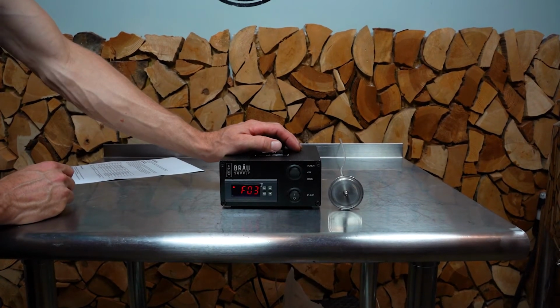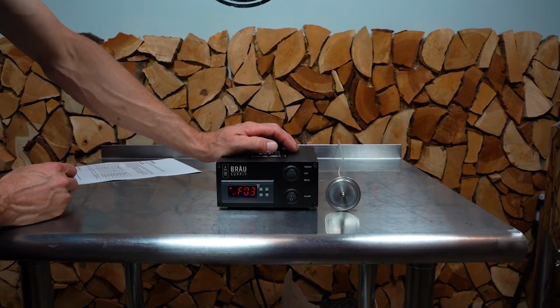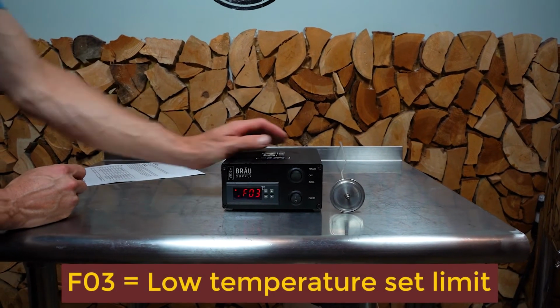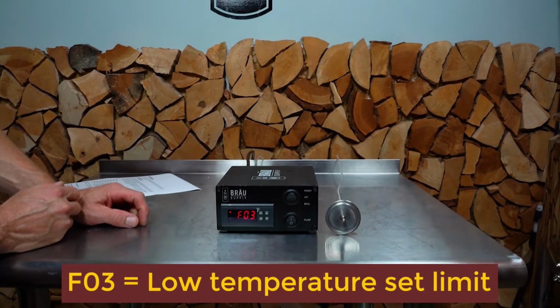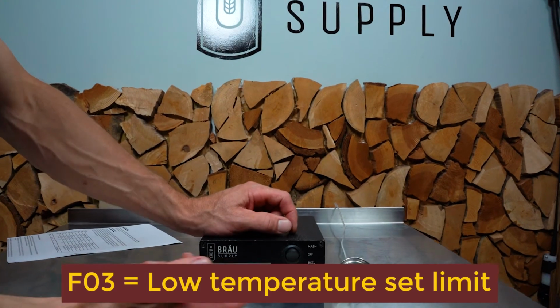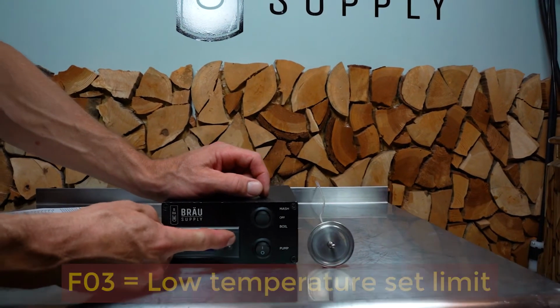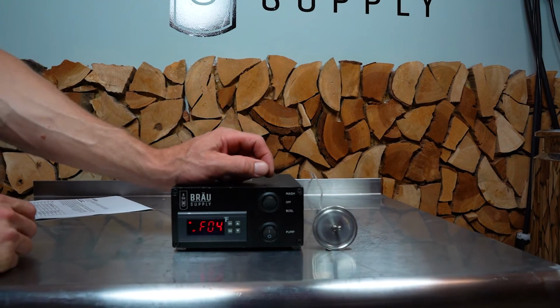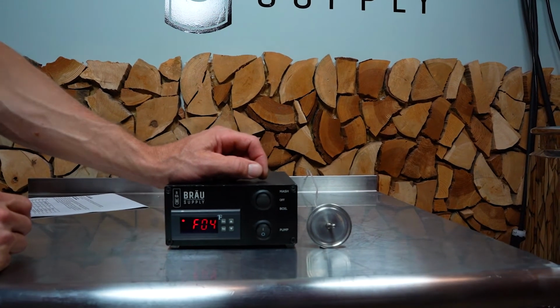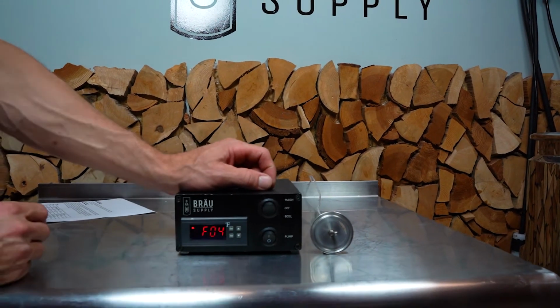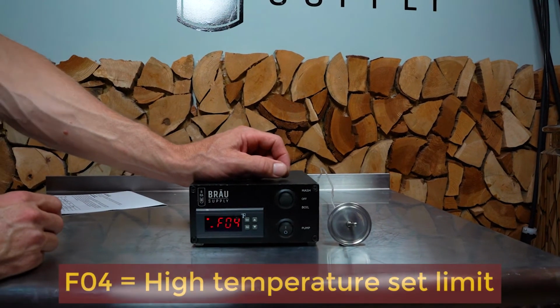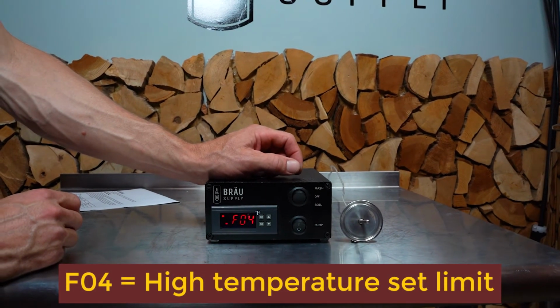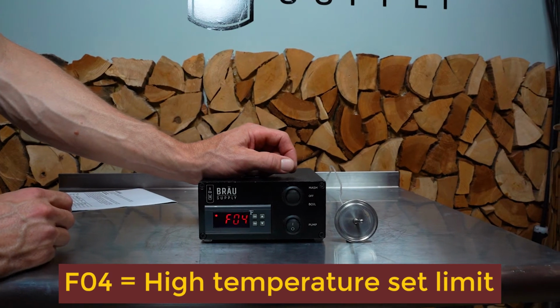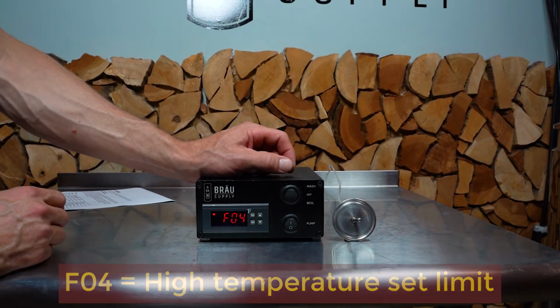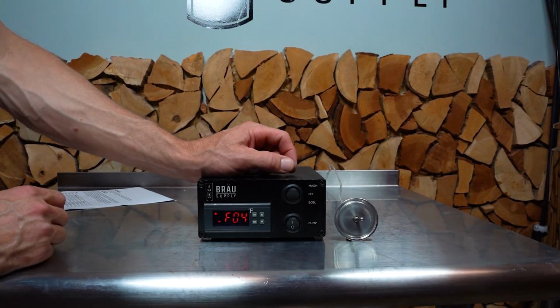F03 is the low temperature set limit. So generally, this is unimportant. I don't even look at what this does, but it's there for you in case you want to change it. High temperature setting limit. So again, this is the highest temperature setting that you can allow on it. So at default, it's set to 212. I don't think we really need to worry about that too much.